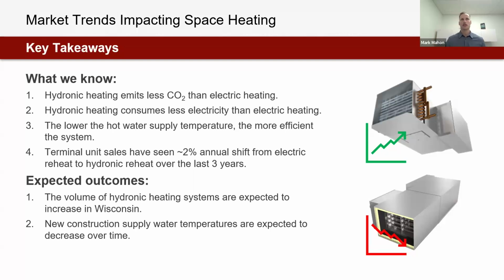So, some key takeaways or thoughts for this first section. One thing that we know generally now in the United States is hydronic heating is emitting less carbon dioxide than electric heating. That's true currently. Hydronic heating is consuming less electricity than electric heating because of that elevated COP that we can maybe get from ground source heat pumps. So that's a potential lever to pull and a trend that we see. Generally, the lower the hot water supply temperature, the more efficient the system.